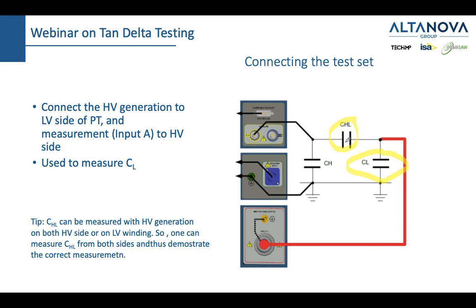You can measure CHL from the high voltage side, then repeat that measurement from the low voltage side, and see if the number is the same. Up to a third or a fourth decimal, it should be the same. Another way to make sure you are testing correctly is to measure CL, then measure CHL, and then with one shot measure the sum of CL plus CHL. If you sum up these two capacitances and get the same number as when you measure the sum, it means that you are performing the test correctly.